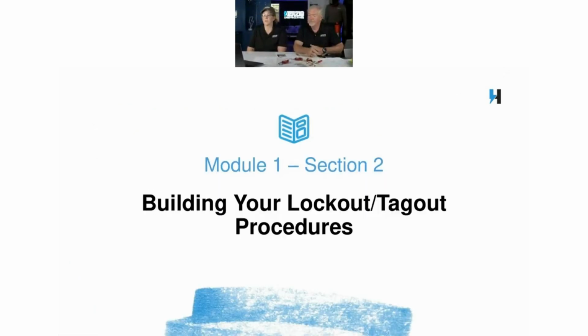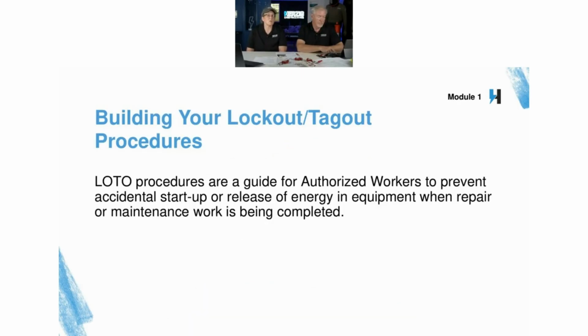So when you're building your lockout, tagout procedures, the first thing you're going to do is identify what hazardous energies are in your facility. There are many variations on equipment, but you'll have some basic energy sources - electrical, pneumatic, hot water or steam, hydraulic. You could also have a variety of fuel sources, like natural gas, propane, fuel oil, or diesel.